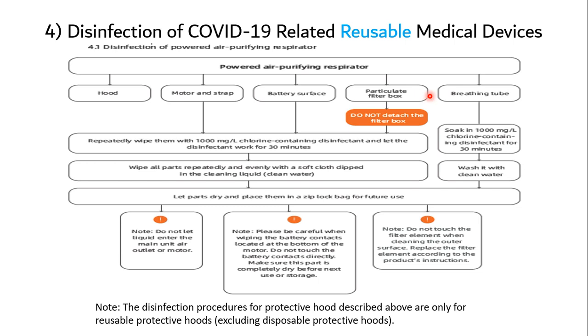For these three, we will deal with them the same, but be careful, do not detach the filter box. You need to repeatedly wipe them with 1000 mg per liter chlorine-containing disinfectant and let the disinfectant work for 30 minutes. Wipe all parts repeatedly, and then wipe with a soft cloth dipped in clean water. Let the parts dry and place them in a lock bag for future use.